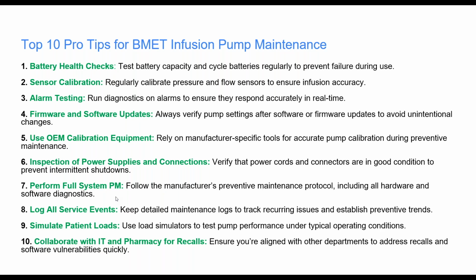Perform the full system PM, right? I mentioned alternate equipment management or maintenance. Certainly, once you have enough information, either from your hospital, if it's your hospital system's policy to only use your data, or from other bodies that have credible information as well, if your hospital policy allows for that, then move to an AEM and make sure that you're tracking how well that AEM performs in comparison to what the expectation from the manufacturers would have been.